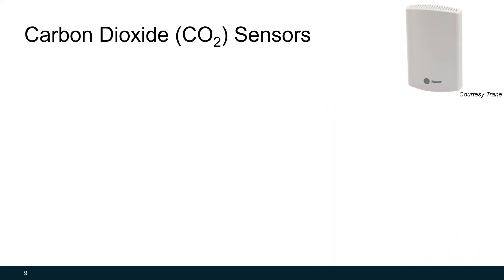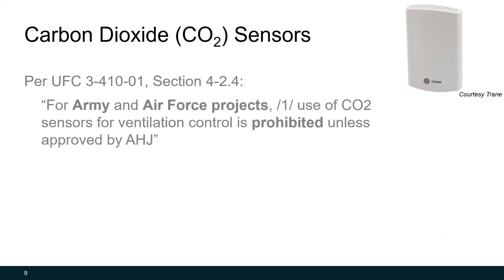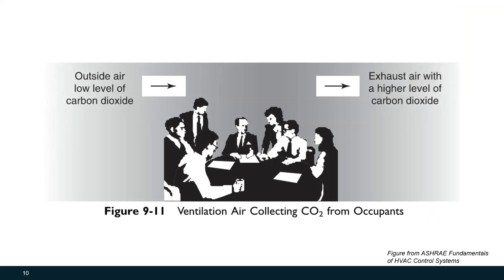The most common DCV sensor is the carbon dioxide sensor. With that said, per UFC guidelines, Army and Air Force projects, the use of carbon dioxide sensors for ventilation control is prohibited unless approved by the authority having jurisdiction. However, especially in the commercial world, we use carbon dioxide sensors a lot for determining occupancy. The idea is pretty simple: we want to bring in outside air with a low level of carbon dioxide and exhaust the air in a building with a higher level of carbon dioxide from what we all breathe out.